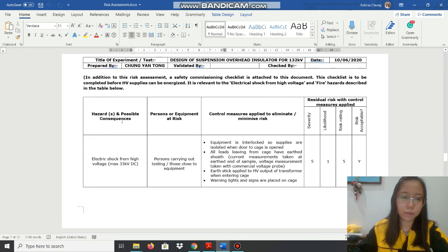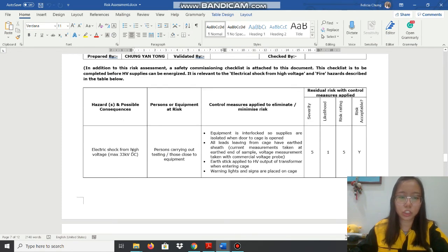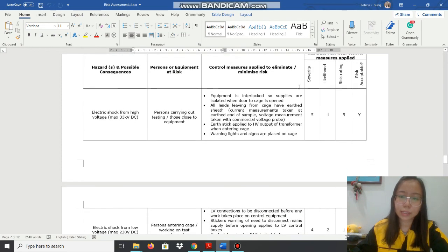For the hazard of electric shock from the high voltage, we can minimize this risk by interlocking the equipment, so the supply is isolated when the door to the cage is open. The severity of occurrence is rated 5, and the risk rating is also 5.